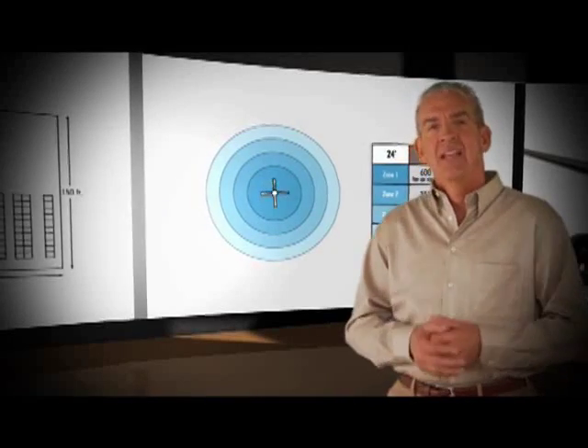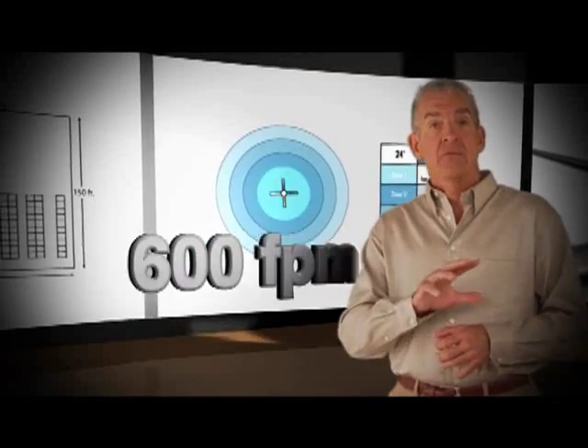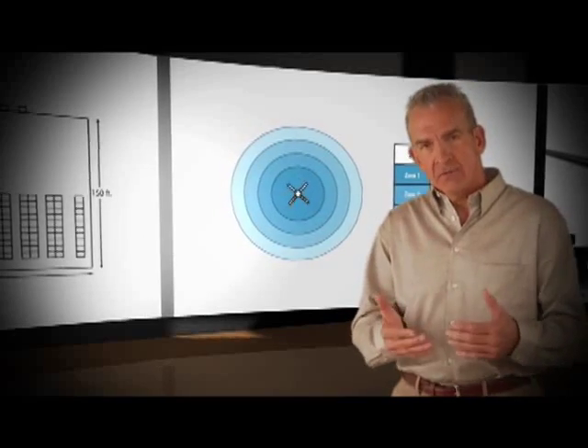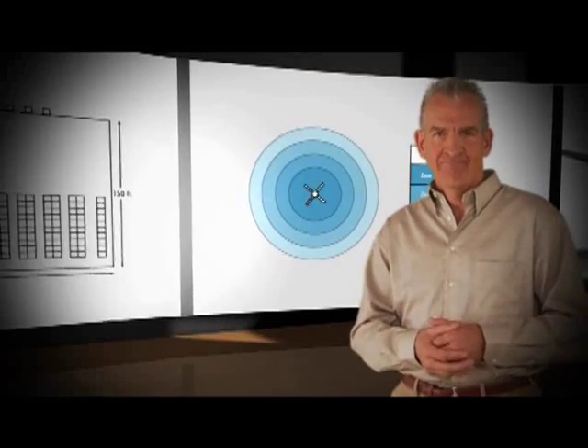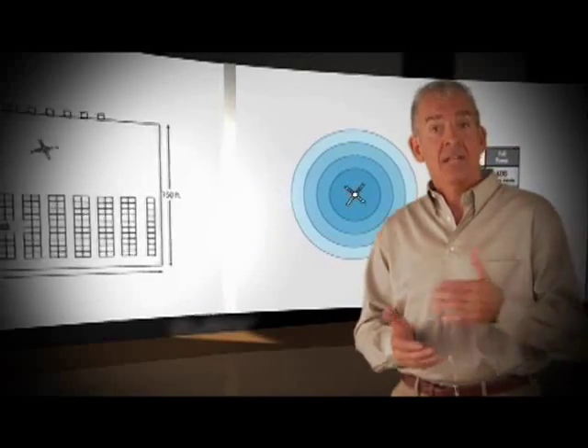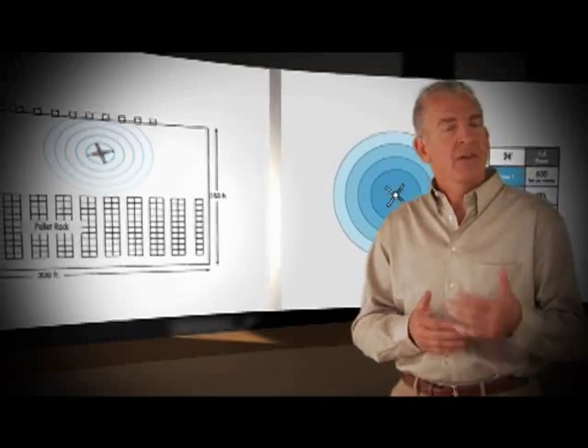For example, a 24-foot fan would range from 600 feet per minute in the inner zone to 200 feet per minute in the outer zone. This allows us to match fan size and air speed to the floor plan to create the perfect fan arrangement for your facility.